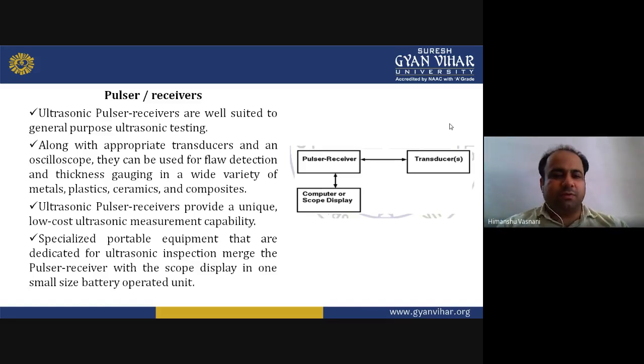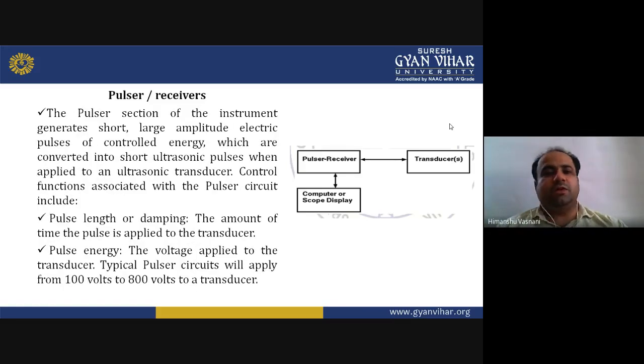Now, ultrasonic pulser receivers provide a unique, low-cost ultrasonic measurement capability. You can see they have specialized portable equipment dedicated to ultrasonic inspection, merging the pulser receiver with the scope display in one small, battery-operated unit. This is another application. The pulser section of the instrument generates short, large amplitude electric pulses of controlled energy, which are converted into short ultrasonic pulses when applied to an ultrasonic transducer.